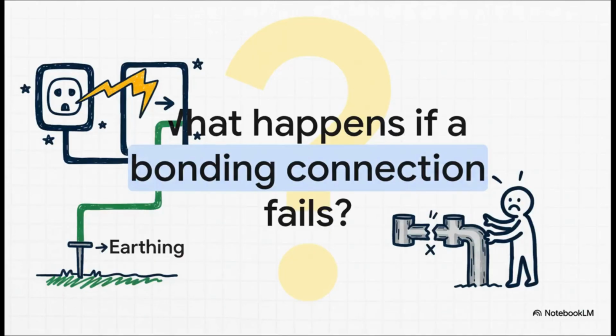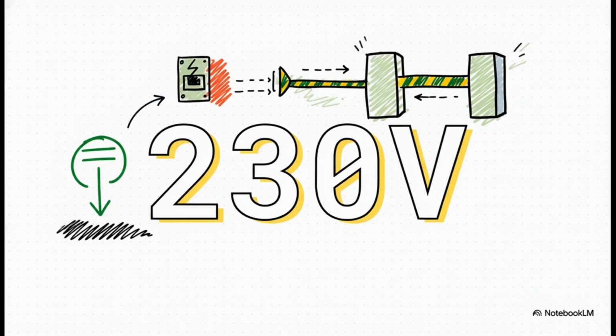But what if just one of those little links, one of those crucial bonding wires, is missing? Or maybe it fails over time. This is the moment a totally safe situation can become incredibly dangerous in the blink of an eye. You see, without that bonding, you can get a massive, and I mean potentially lethal, voltage difference appearing between two separate metal parts. We're talking the full 230 volts of a standard electrical supply.